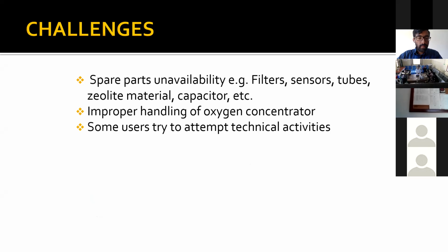Okay, so these are the major challenges that we have at our facility. The spare parts unavailability, for example the filters, sensors, tubes, zeolite material, capacitors, and I will mainly go to zeolite materials. We have up to 40 oxygen concentrators, but 24 are working properly, and 16 have the problem of needing their zeolite materials replaced. So this is our major challenge at our facility.